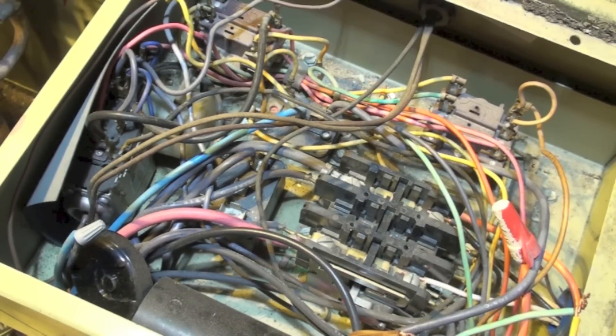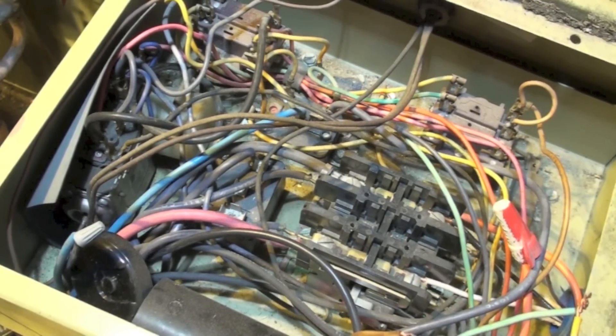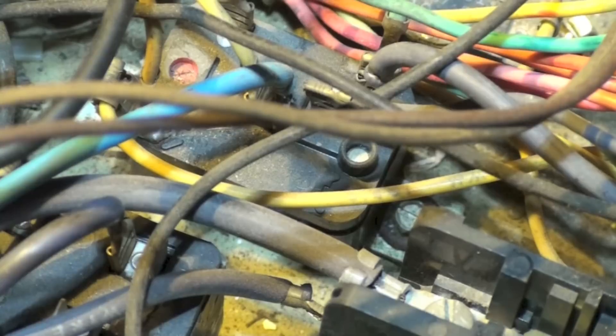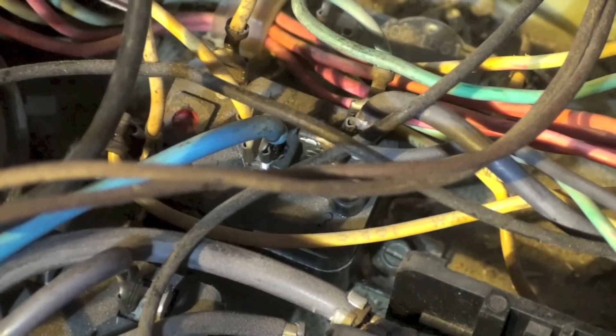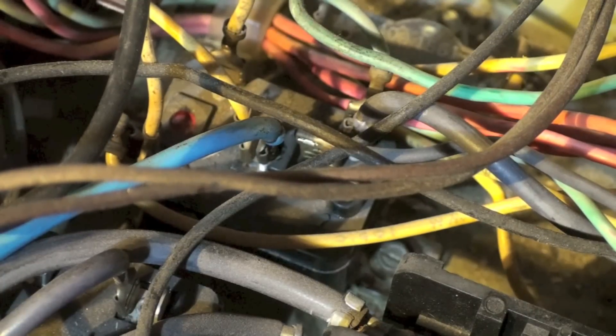Here's the answer to that silly little problem I showed you a couple of days ago. See that old black relay — what we call a peanut relay, right there. That's a nice little sticky peanut relay. I kind of hate those things because this is what they commonly do: they will stick on like that.